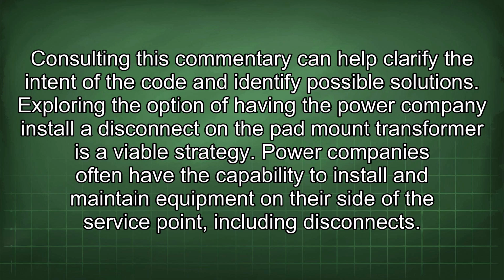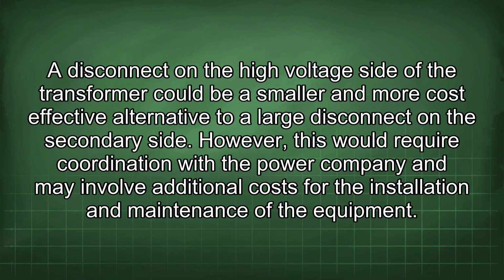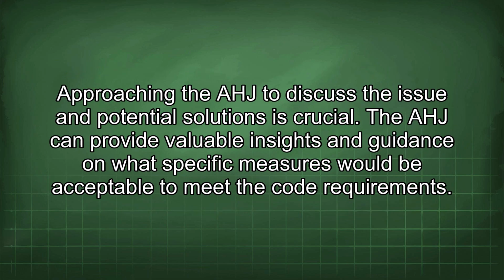Exploring the option of having the power company install a disconnect on the pad mount transformer is a viable strategy. Power companies often have the capability to install and maintain equipment on their side of the service point, including disconnects. A disconnect on the high voltage side of the transformer could be a smaller and more cost-effective alternative to a large disconnect on the secondary side. However, this would require coordination with the power company and may involve additional costs for the installation and maintenance of the equipment. Approaching the AHJ to discuss the issue and potential solutions is crucial.